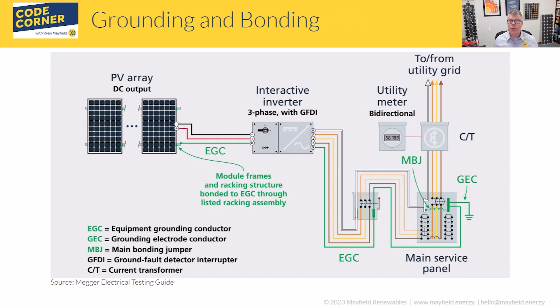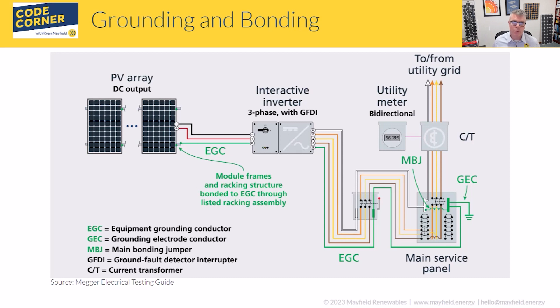Let's look at the big picture and understand some of these terms. With grounding and bonding, the terms are very similar and there are small differences, so you have to pick up on those differences to make sure you're using them correctly. Going from left to right on this image, we have the EGC — the equipment grounding conductor — and what it's doing is bonding all of the metal equipment together. It could more aptly be named an equipment bonding conductor, but it is called the equipment grounding conductor.